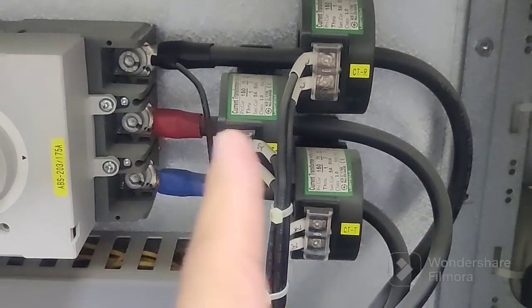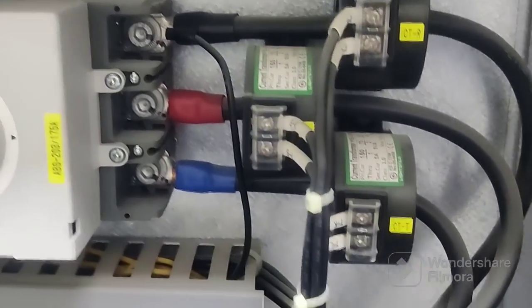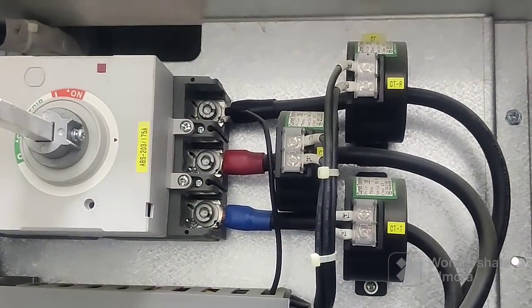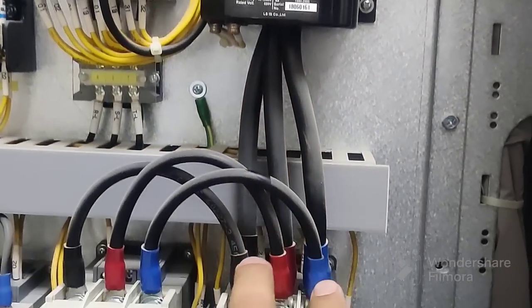One cable is going through one CT and the second cable is passing through the other CT, so we have a total of three CTs — one CT per phase. The outgoing is coming here — this is the main current transformer CT. So this one is carrying single-phase ampere for each line.